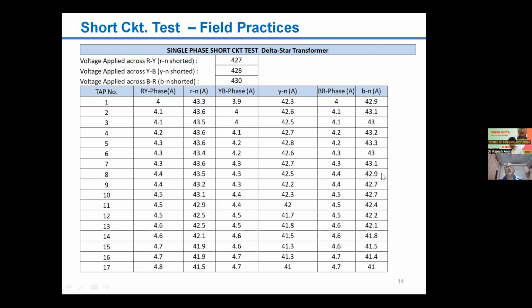There is a pattern which you see on this table, and this trend in itself gives information that the transformer is healthy. If there are some issues, the results will vary and there will not be a smooth trend. There may be some variations here and there. Accordingly, we will analyze and see what kind of issues may be there if some problem has occurred with the transformer winding. Next.